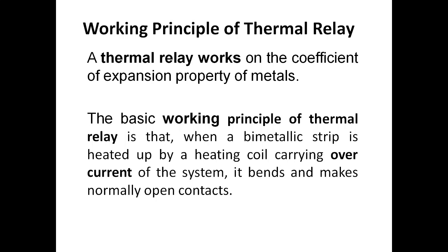A thermal protection relay works on the coefficient of expansion property of metals. The basic working principle of a thermal relay is that when a bimetallic strip is heated up by a heating coil carrying overcurrent of the system, it bends and makes the normally open contacts close.